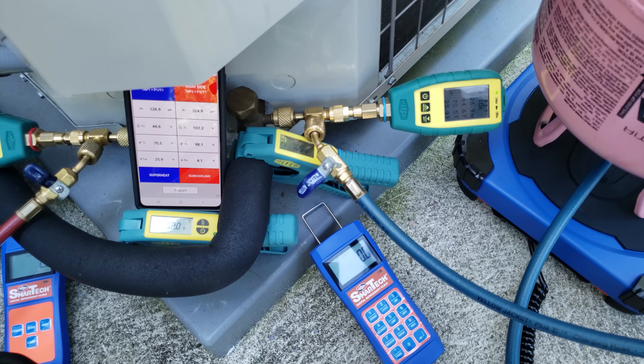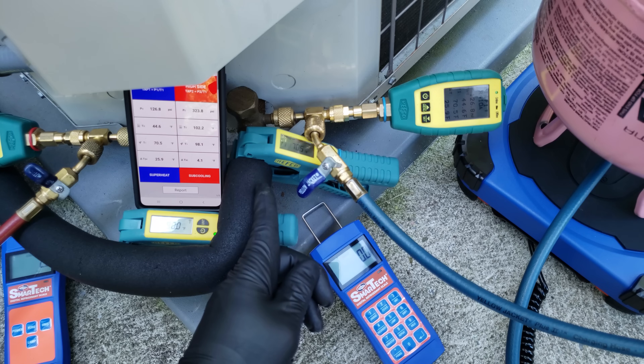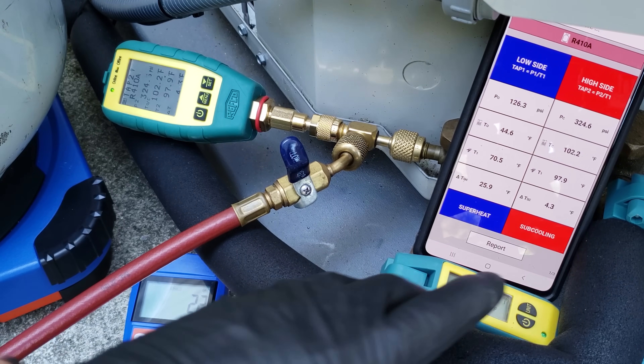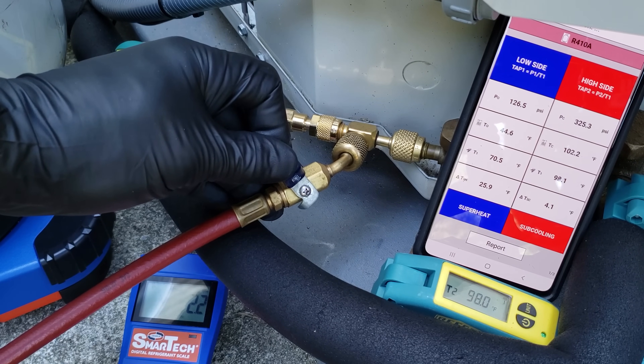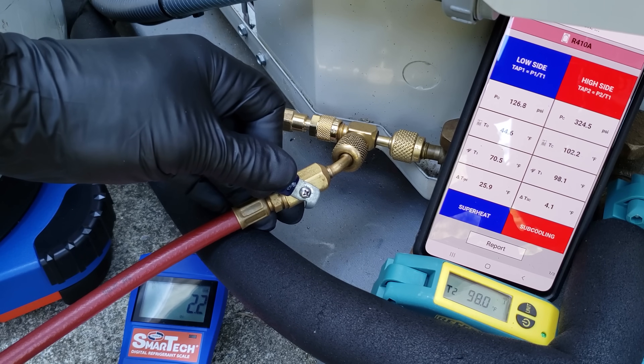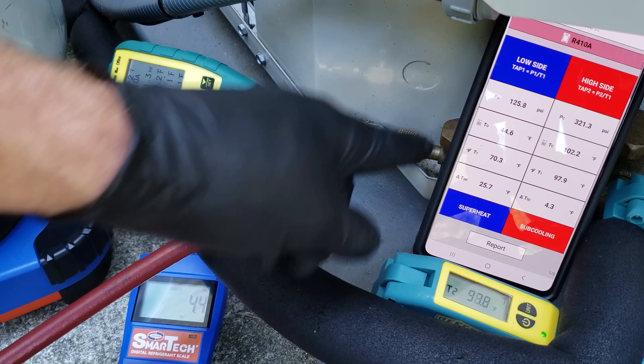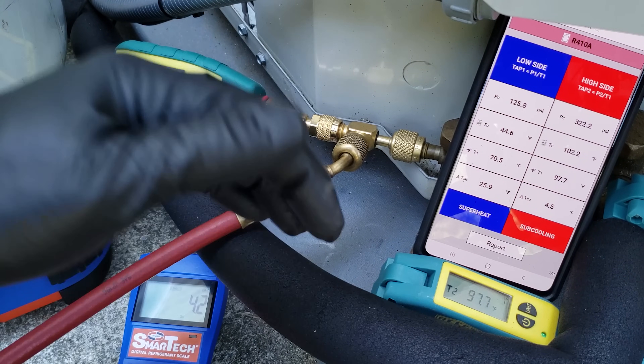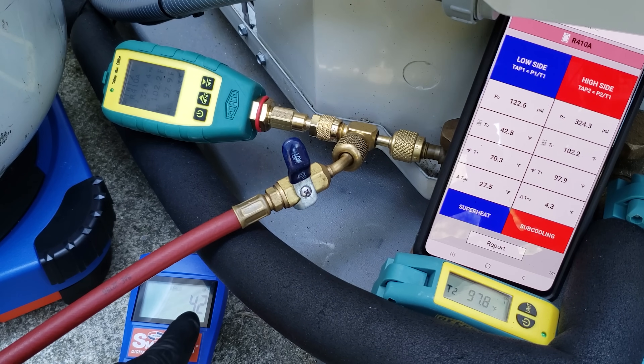So liquid refrigerant is going to go from the system into the bottle. So far the sub cooling has lowered a little bit. Superheat is about the same — I'm going to recover a little bit more. You want to avoid recovering a lot of refrigerant this way because you'll lose oil out of the system, since oil is mixed with the liquid refrigerant and will come out into the bottle. Only do this a little bit if you're just adjusting the charge on an overcharged system. We took out four ounces total; now superheat is high, sub cooling is low, and both low and high side pressures are low.